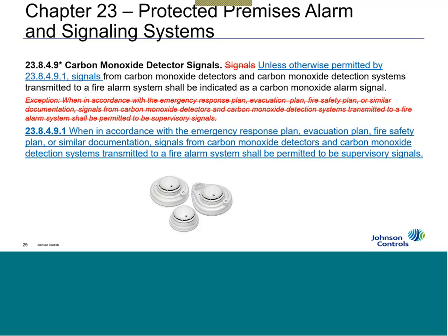And this, by and large, now is a requirement in our code today. You can't bring these in as supervisories, as troubles, or fire alarms. They're going to be identified as what they are, carbon monoxide. Now, there are some cases where the building owner has a different emergency response plan, and they could come in as supervisory signals, but I see that seldom. I've seen that seldom used here in what we're doing.